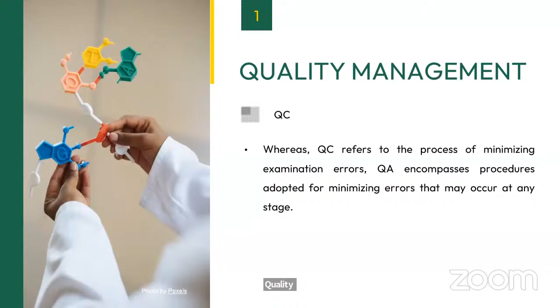The first essential in setting up the internal quality control of a test procedure in the laboratory is to select a proper IQC procedure to implement, choosing the statistical criteria, control rules, and the number of control measurements according to the quality required for the test and the observed performance of the method. So when you are setting up internal quality control practices or procedure in your laboratory, you must have various prerequisites. You should have appropriate quality control material. You should define which controls you are going to use, how many times you are running the control, what will be your acceptable criteria, how you are going to reject the quality control runs, how you are going to do the troubleshooting.